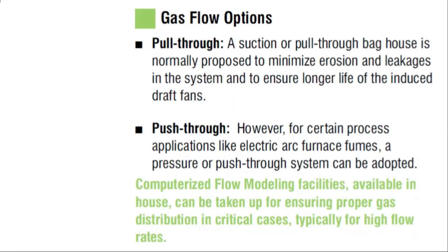Gas Flow Options — Pull-through: A suction or pull-through bag house is normally proposed to minimize erosion and leakages in the system and to ensure longer life of the induced draft fans. Push-through: However, for certain process applications like electric arc furnace fumes, a pressure or push-through system can be adopted. Computerized flow modeling facilities available in-house can be used to ensure proper gas distribution in critical cases, typically for high flow rates.